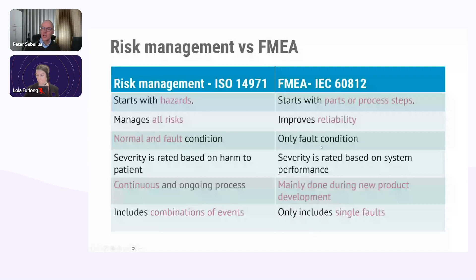Well, let's take a look and try to put ISO 14971, product safety risk management, into the context of FMEA, or the other way around for that matter. So if you have ISO 14971 risk management, the purpose is to prevent harm. That's what we're after here. But FMEA tries to prevent the product from failing and improve reliability. Now, sometimes a failing product can lead to harm, to no surprise.